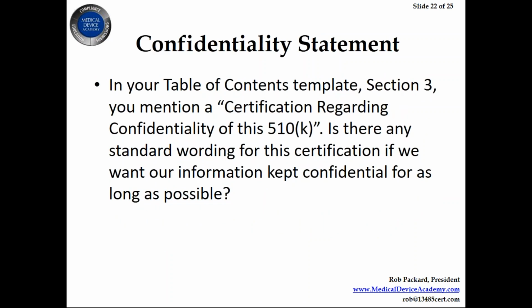Next question was about confidentiality statements. If you want the whole world not to know that you have a 510K pending, what you should do is fill out a confidentiality statement according to the regulations and include it in your 510K submission. So I usually include that in Section 3 as one of the documents.